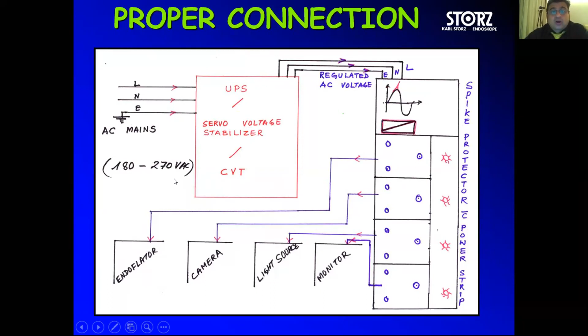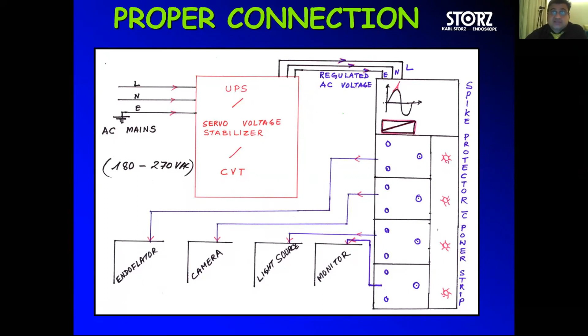Now, how do we make the connection? This is a simple line diagram to understand. This is my AC mains, which is coming in. From the AC mains, you put any of these, best would be a UPS, uninterrupted power supply, which you use for desktops, online or offline, or a CVT, constant voltage transformer. And from here, you connect a spike protector, which looks like an extension board. From the spike protector, you start connecting your different components: endoflator, camera, light source, monitor, etc. This will safeguard your equipment. Do not run the equipment directly from the AC voltage. That will not take care of spikes and surges, and especially in small developing countries, B tier, C tier cities, these issues are happening.